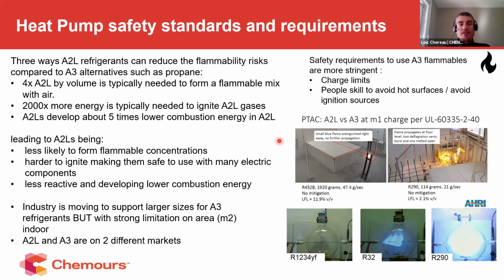This is mostly driven by the LFL, the lower flammability limit of the refrigerant, that needs to be looked at here. With an A2L, there is about 5 times lower combustion energy compared with an A3, and this is why an A2L is much lower in terms of flammability risk when you look at this type of HFO blends.